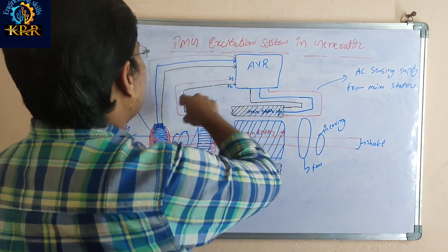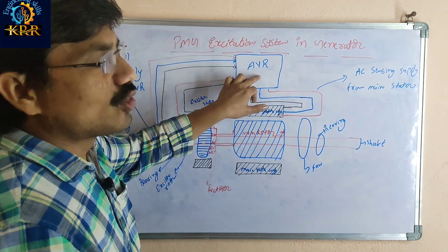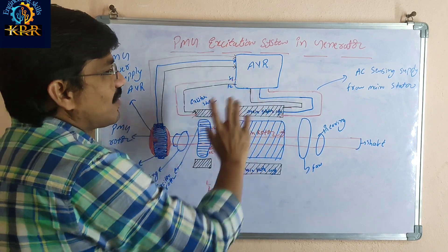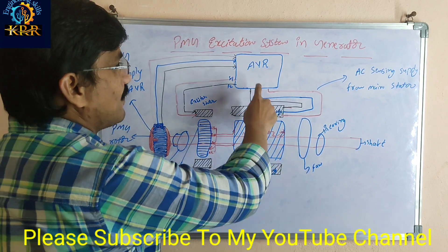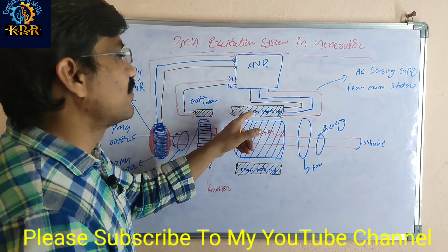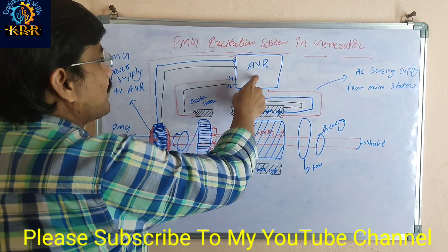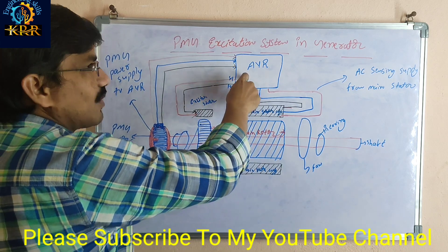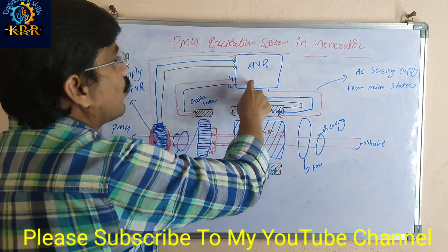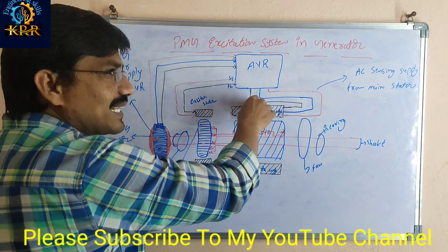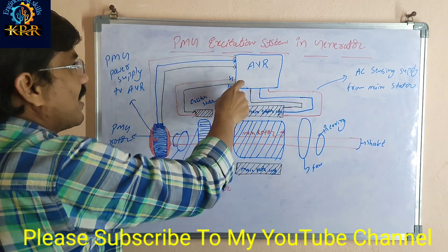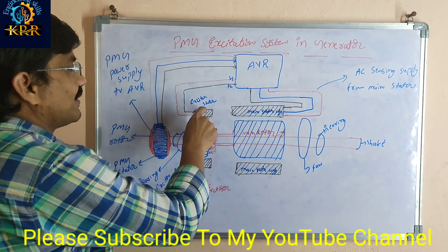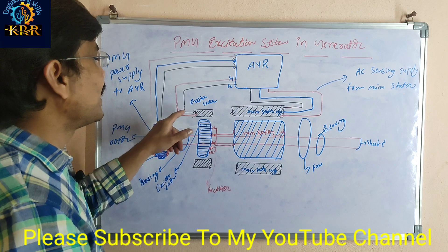The PMG generator supplies power to the Automatic Voltage Regulator. The AVR receives the voltage sensing from the main stator — how much voltage is coming. If low voltage is coming, it applies over-excitation; if high voltage is coming, it applies under-excitation. Accordingly, it provides power to the exciter stator.